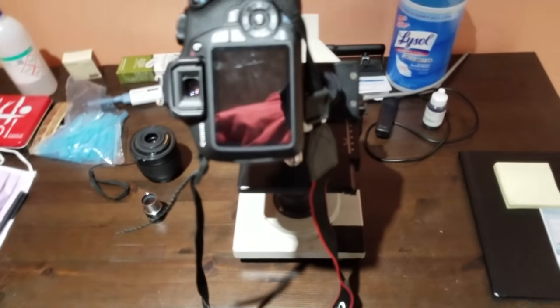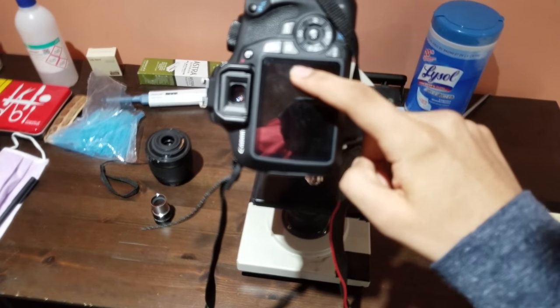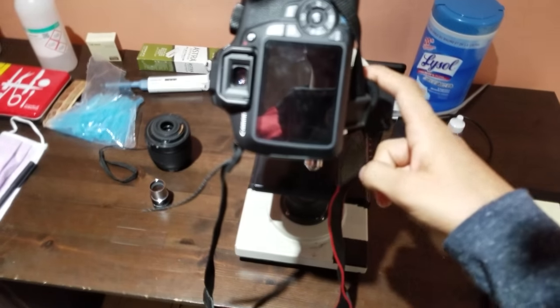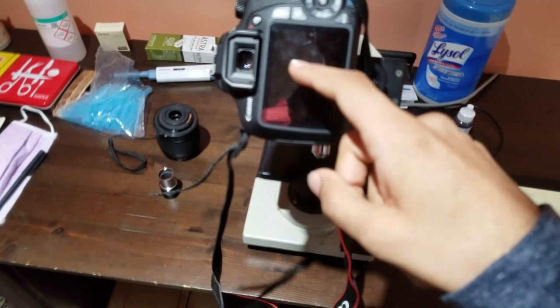and then you can just use this camera as normal, with the exception that the camera will not be able to focus anymore. So you have to focus only with the microscope. And also, when you focus using the camera, it's a different focal setting compared to when you focus with your eyes.